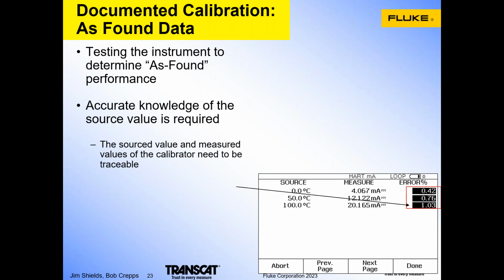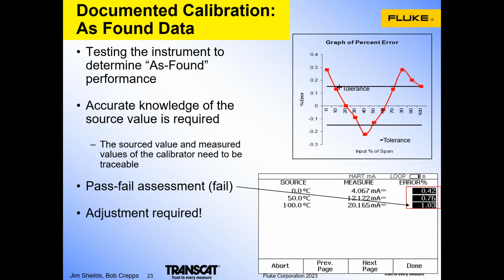Accurate knowledge of the source is required. The source value and measured values of the calibrator need to be traceable. And the pass-fail assessment indicates that this device failed and it needs adjustment. And if I take a look and graph the measured values versus the test tolerance, you can see that a couple of these points were out of tolerance and that adjustment is required.